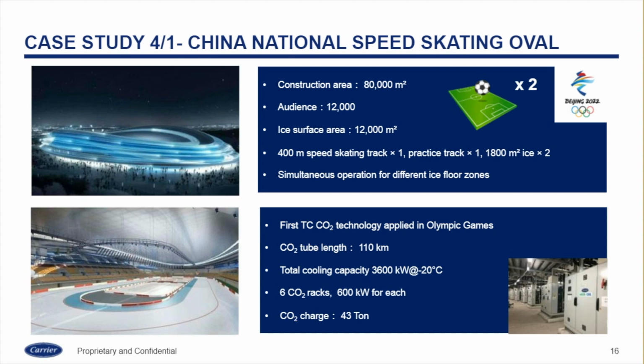And the total project size is about 3600 kilowatts of cooling capacity, and we are equipping about 6 CO2 racks, at 600 each for the cooling capacity, and the CO2 total charge is 43 tonnes for the system. Okay. Next page, please.